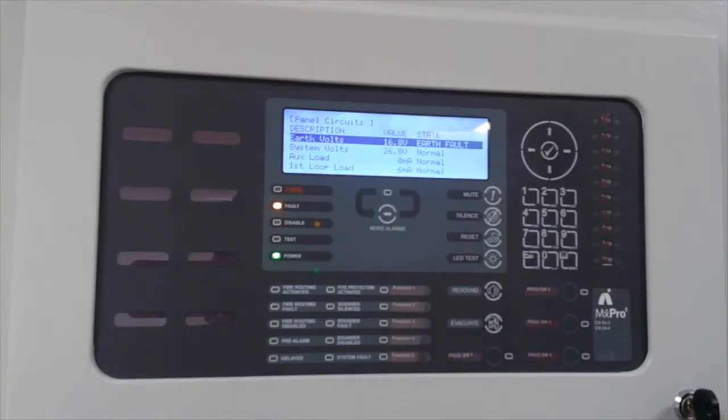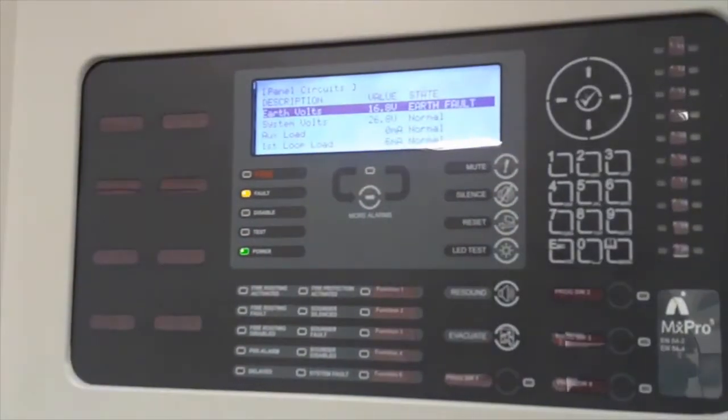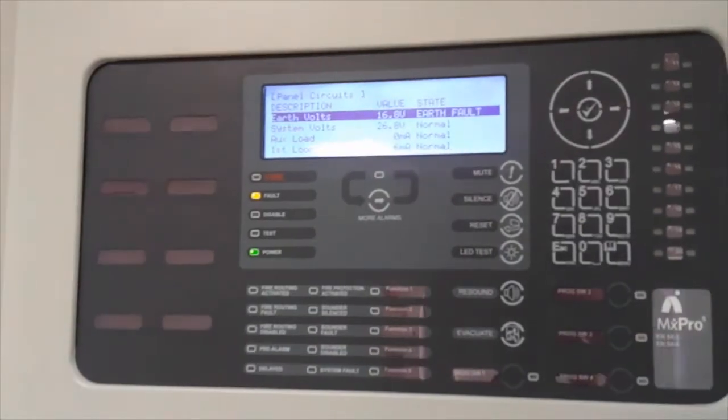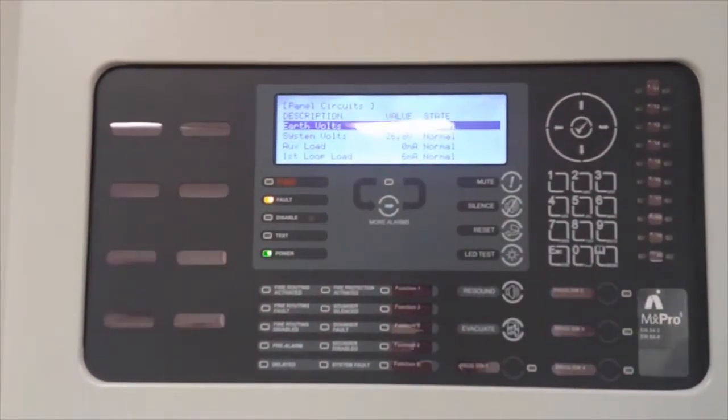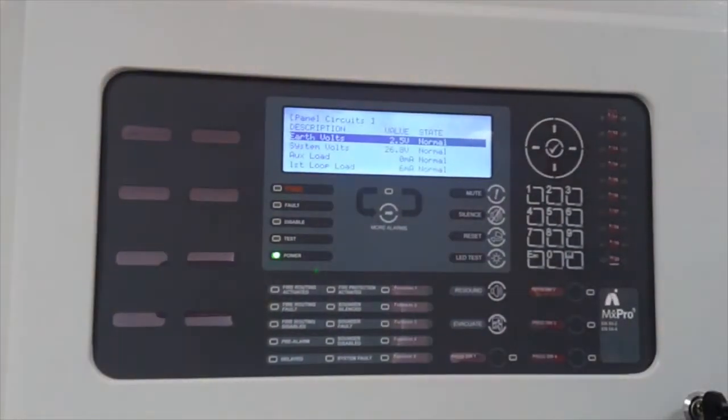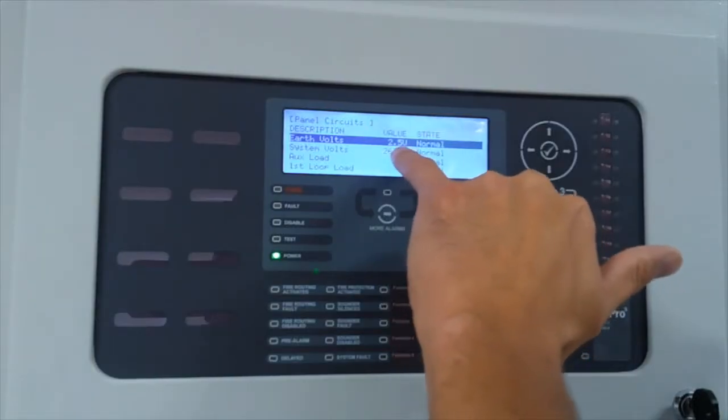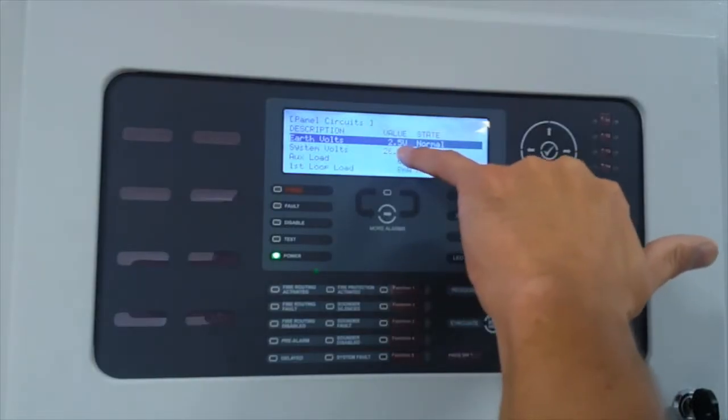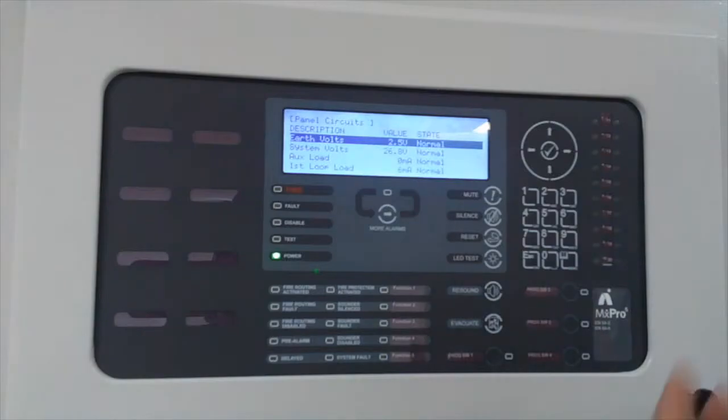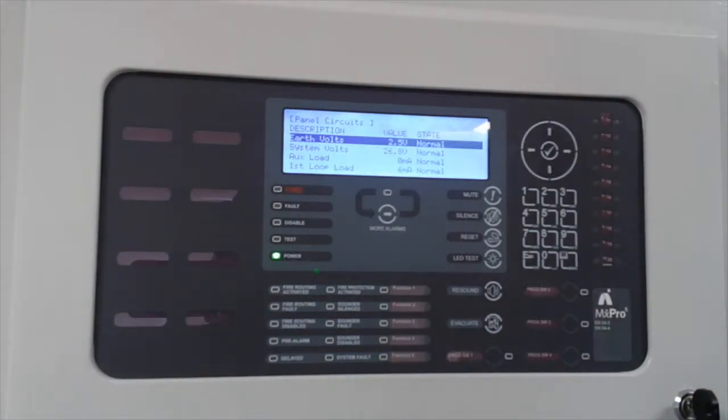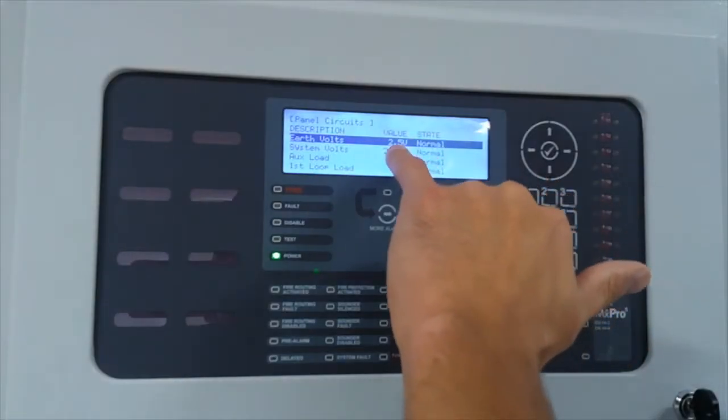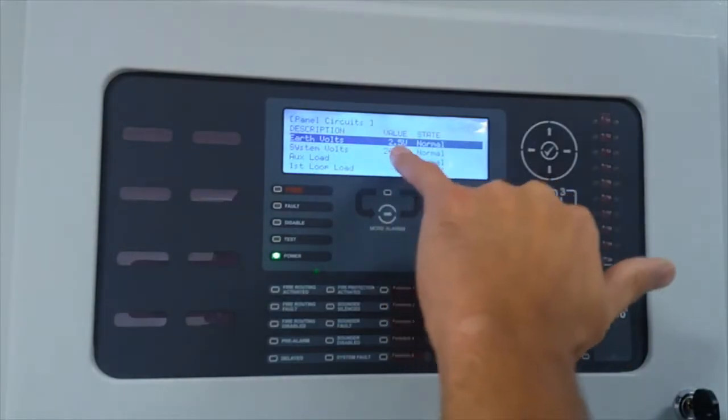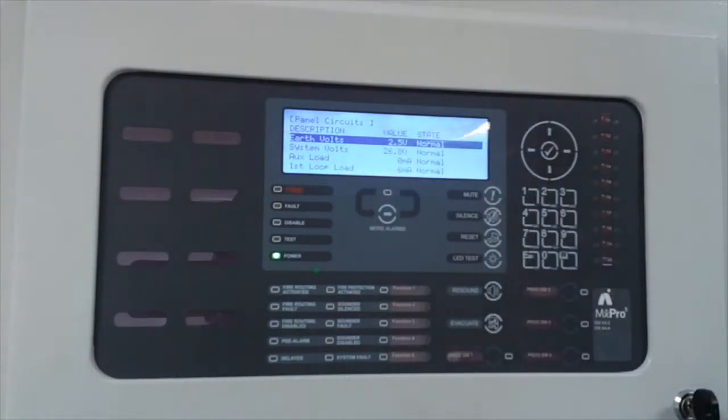We are seeing it is a positive conductor at the ground because if we clear that earth fault, it is going to clear the earth fault from the system. All faults are not latching. You can see the normal reading is 2.5 volts. So if that earth voltage goes greater than 3.5 volts or say 4 volts, that is a positive conductor at the ground. If this voltage drops less than 1.5 volts, then it is a negative conductor at the ground.